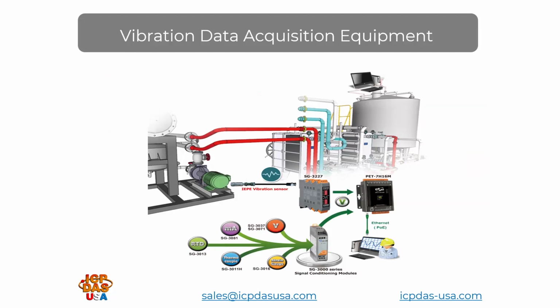The system here uses the IEPE vibration sensor to monitor the bearings of a motor. The SG3227 is a 2-channel IEPE accelerometer signal conditioning module. It has built-in 2 groups of dip switches which can be individually set for 2 channels to provide 2 milliamp, 4 milliamp, 6 milliamp, and 10 milliamp excitation currents to the accelerometer. And the built-in amplifier can provide anywhere from 1 to 10 to 100 times gain. The LED lights can clearly show whether the status of the sensor is normal, open circuit, or short circuit to avoid wiring errors.